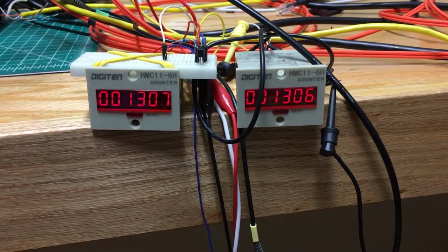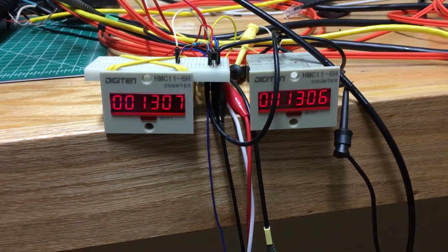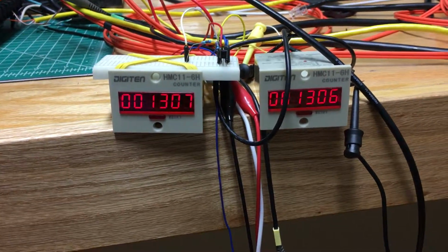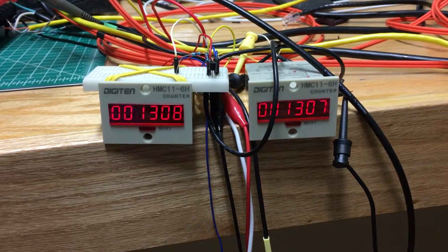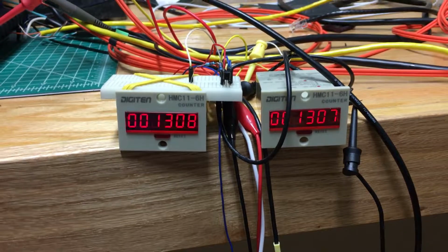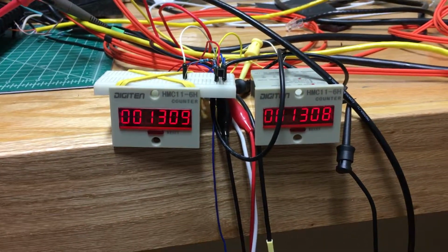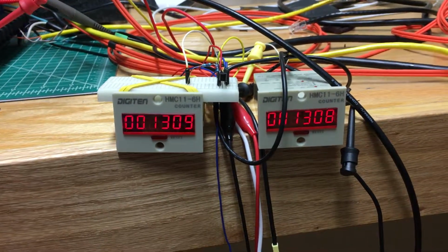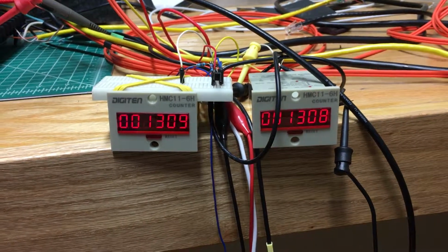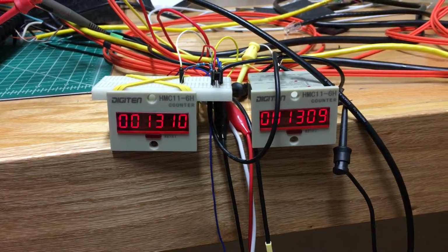And I think that if I could coordinate or synchronize the moment that I cut the fiber with the moment that the trip is sent, which is not something I can do right now because I'm pulling the fiber more or less at a random time, and I did that something like 7 or 8 times. But I see here that I'm losing some trip. So of course this is to be expected because the trip duration is very short and I'm sending a whole bunch of them.